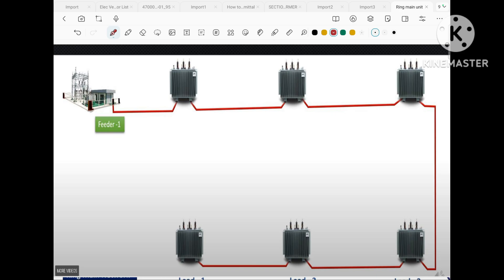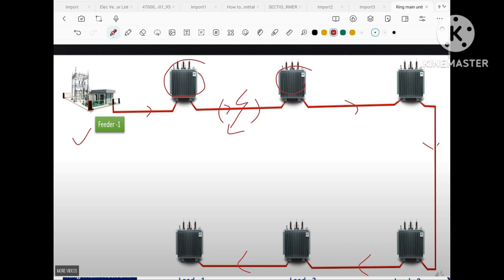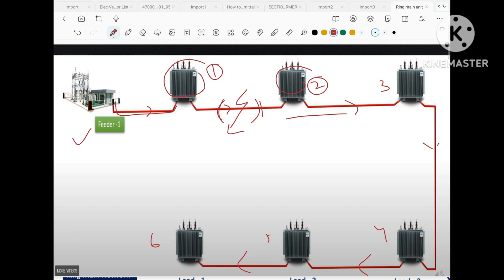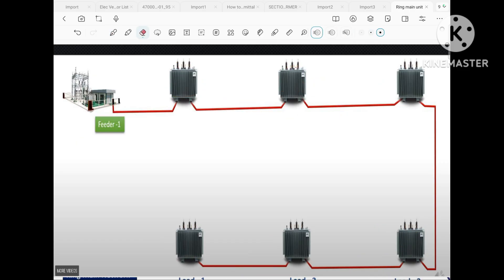Now instead of 13 ampere sockets, we connect a distribution transformer in our radial circuit manner. In a normal condition when the feeder is healthy, load is healthy, and the distribution network is healthy, the power supply will reach every transformer. But suppose there is a fault in the distribution network — the power supply will go to the first transformer, but as the cable has been cut, there will be a blackout in transformers two, three, four, five, and six. So this is not a reliable system. There will be a cutoff of power supply for all other transformers.